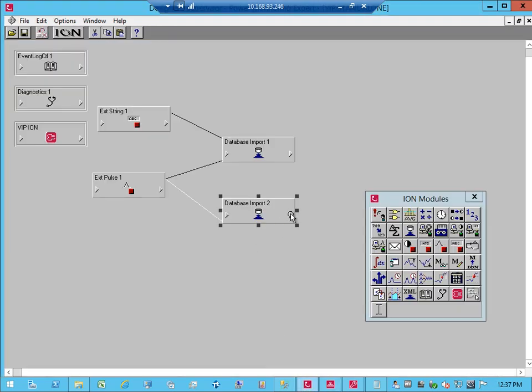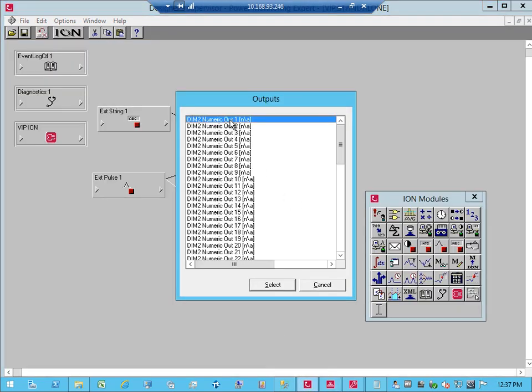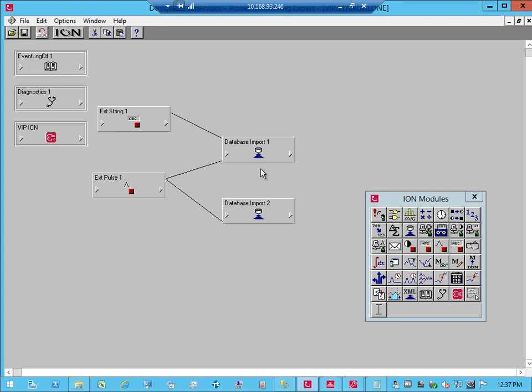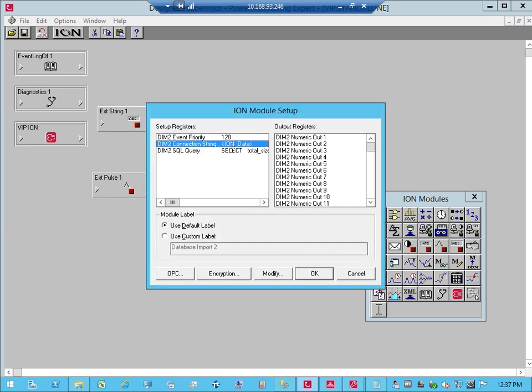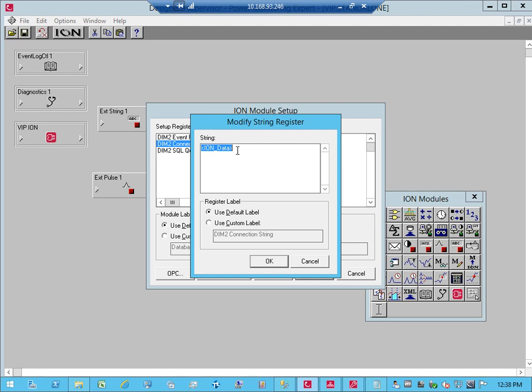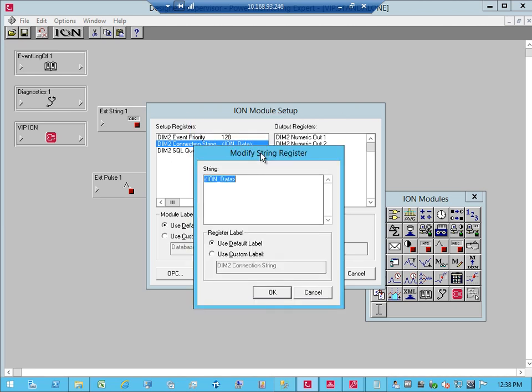the first thing I will notice is that I didn't get my value. I happen to know that to query the database size from the master database, you will need certain permissions. When you use these default connection strings, they're using the report user that's already created in the Power Monitoring Expert database, and it's a read-only user. So if you do need something that has a little bit more privileges, you need to modify this connection string.